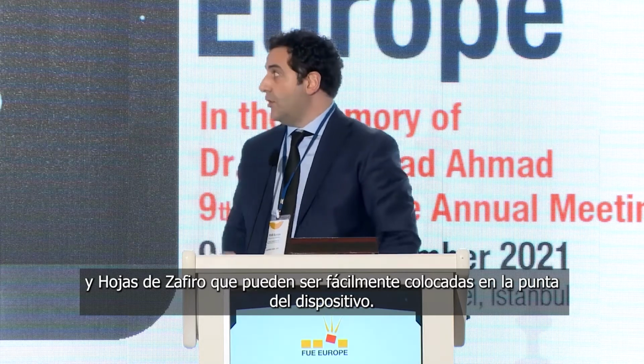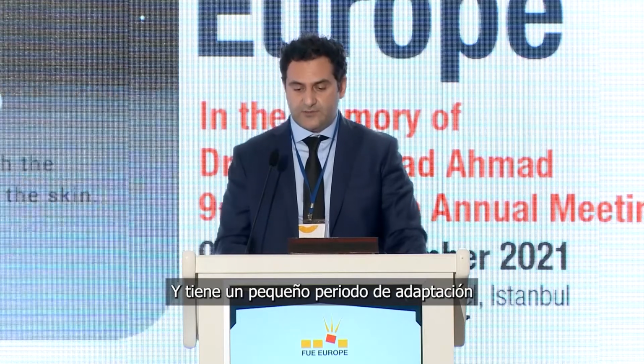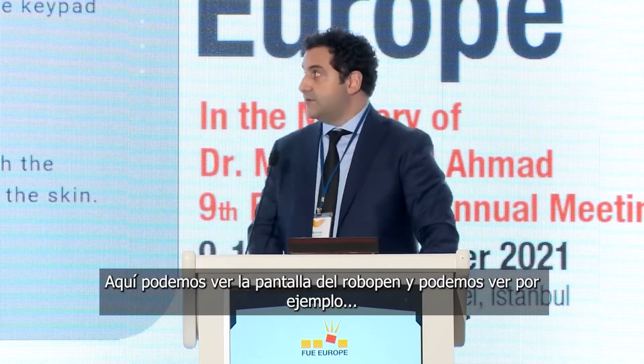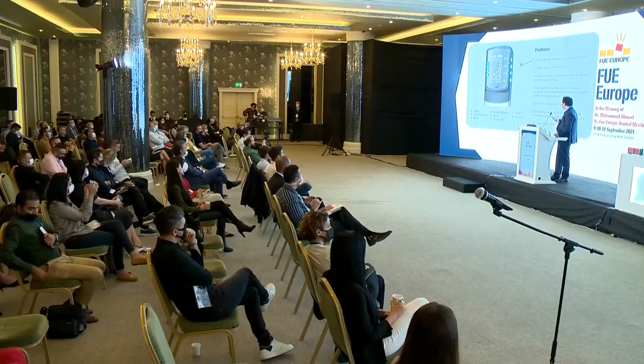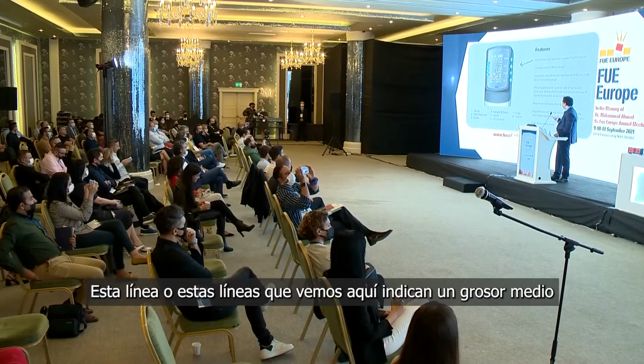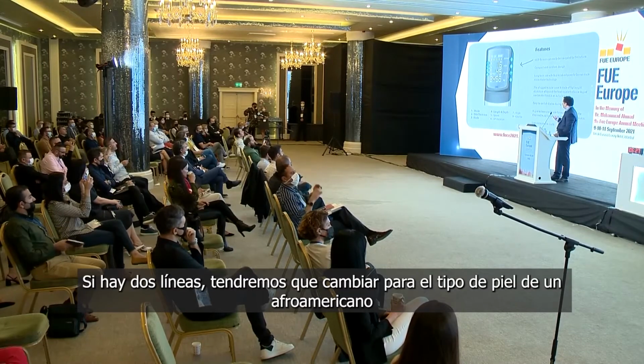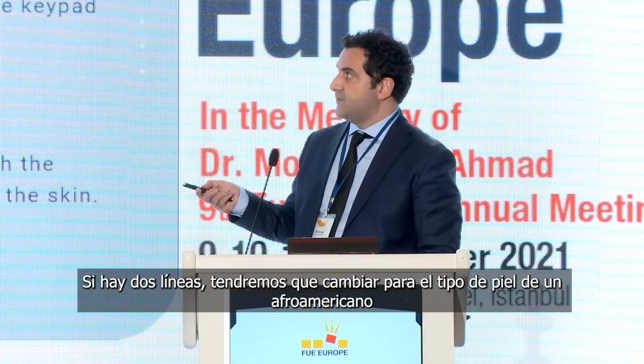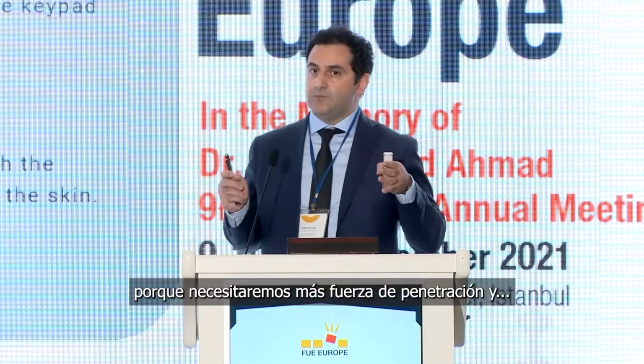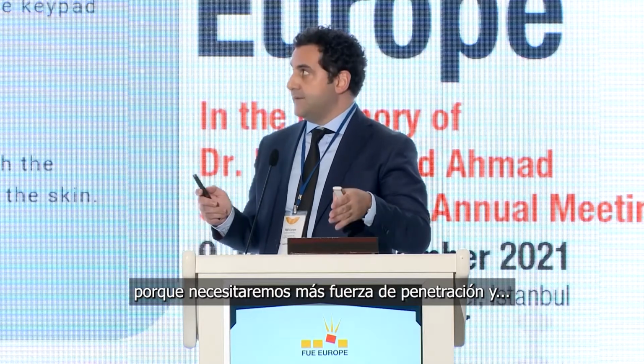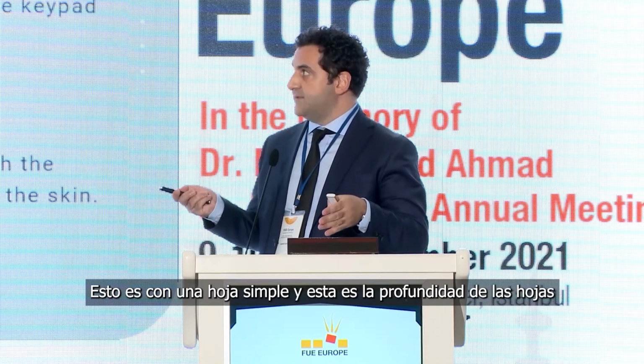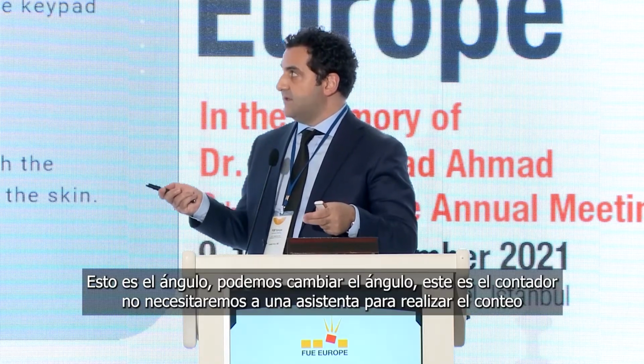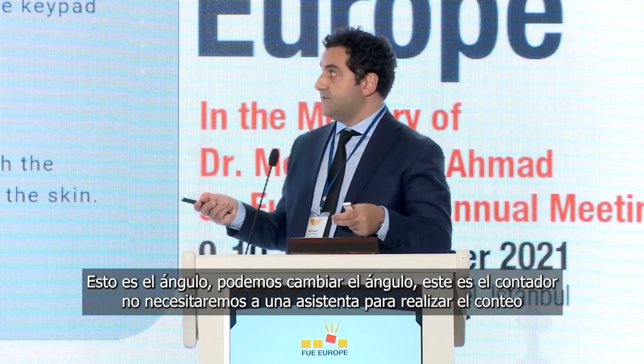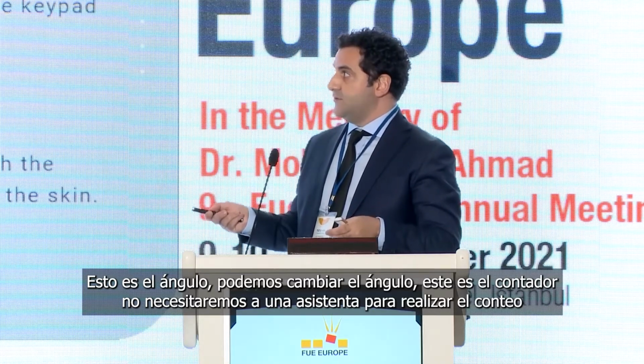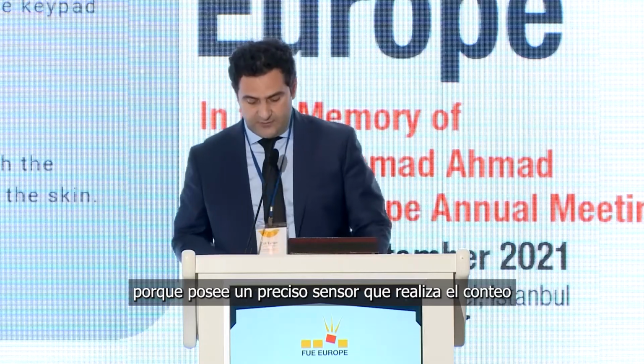It can attach to the tip of the device easily, and there is a short adaptation period. Here is a screen of the ROBOPEN. Here we can see, for example, that 2 lines means medium thickness. If it's 3 lines, you know you have to change this for Afro-American type skins because you will need more penetration force. And this is a single blade, and this is the depth of the blade. These are the angles, you can change the angle. This is the counter. You don't need an assistant to count it because it has a very precise counter sensor.